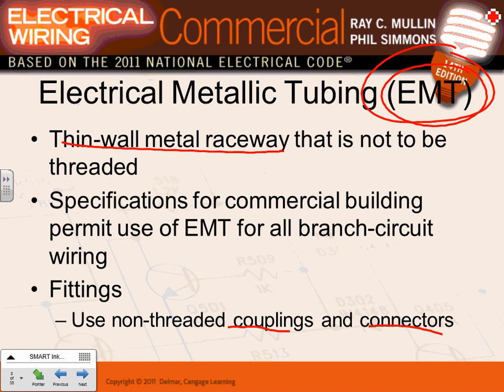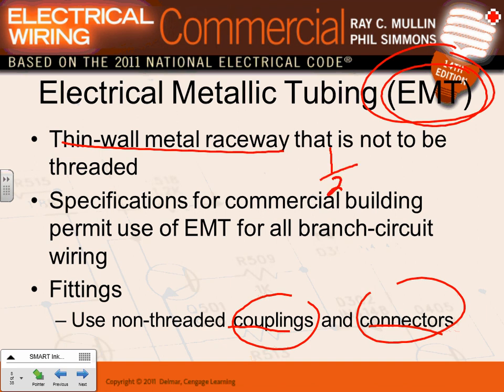The sizes that EMT comes in range from half an inch to four inches - that's a drawback compared to rigid. Can I have a thumbs up? If we go to a commercial building, feeders above ground will be at minimum in EMT conduit. If they need physical protection outside above ground, use rigid. If feeders are underground, your conduit of choice is PVC. Above ground, your conduit of choice is EMT.